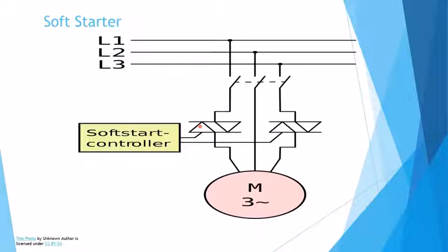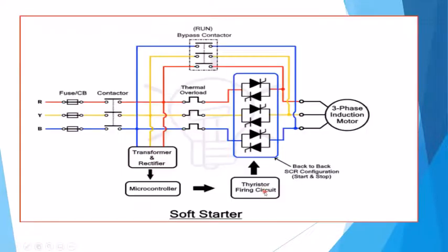Then came out within, I'd say, the 70s, the soft starter, which was basically, these are thyristors, meaning that you had your L1, L2, and L3, and this is just a disconnect switch, it would be between it and the motor. So this is a little bit more detailed drawing of it, but what was happening is these 3 sets of thyristors were in series with the motor, and when you bring your contactor on, what you're able to do is you're actually able to fire how far on the sine wave it is.